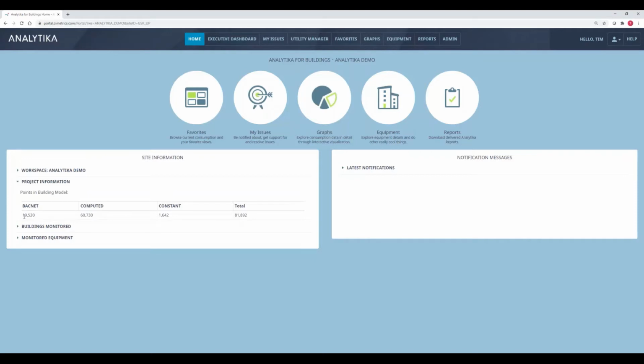In this case, we are taking almost 20,000 points from the system. Analytika is then computing an additional almost 61,000 values from the 20,000 we're polling. These are intermediate values used in our algorithms. We've hard entered into Analytika almost 1,700 values, things like horsepowers for pumps, CFMs for air handlers, etc. These come off the drawings and any other documentation made available to us. These are constants that don't change over time, as opposed to the dynamic data we get from the system live. So the total number of data points we're analyzing at this campus is almost 82,000.